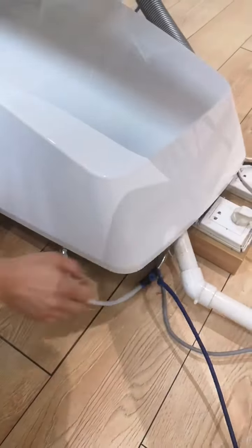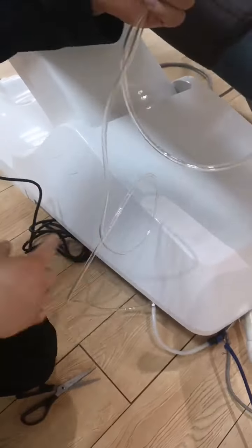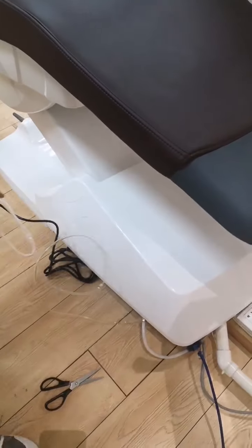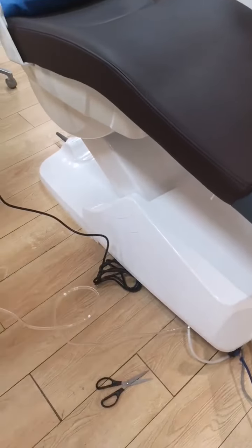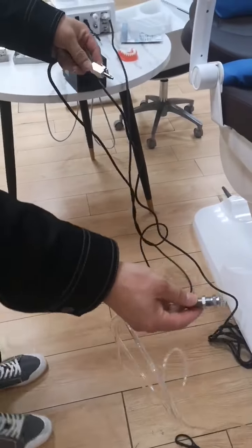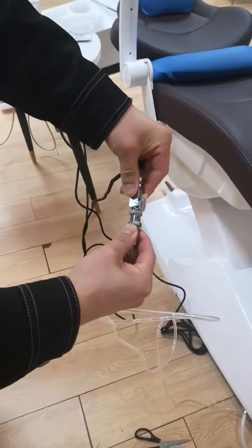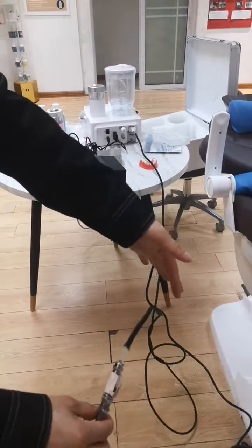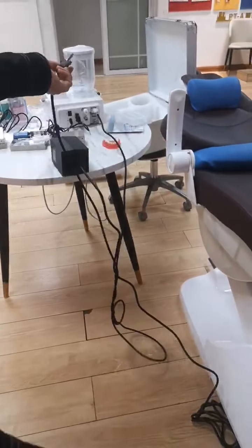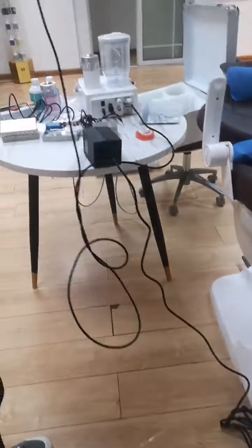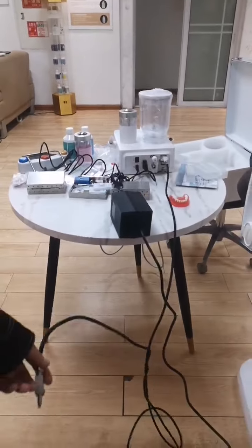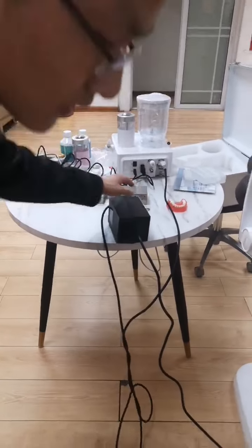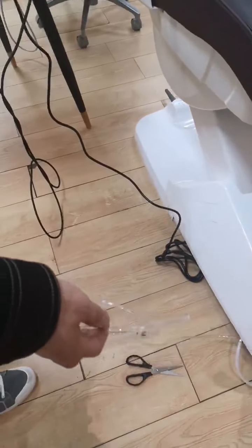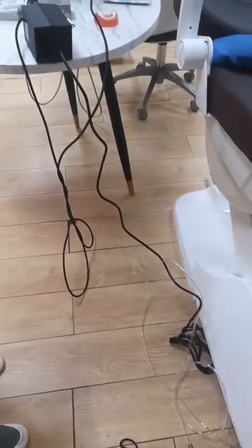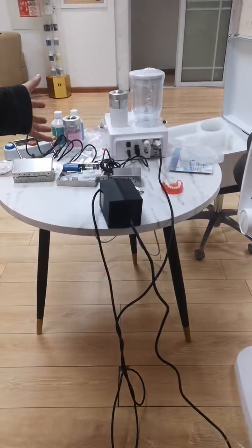Now we put back the cover, and you can see now we have one extra air pipe from the dental chair. So if you are going to use the device, you just connect the air pipe from the device with the air pipe of the dental chair. We connect them together. If you don't want to use it, you just remove them. In this way, we can connect any chair with this pipe. And then when you are going to use the machine, it's very easy. Okay, so that's all about how to install the device. Thank you.